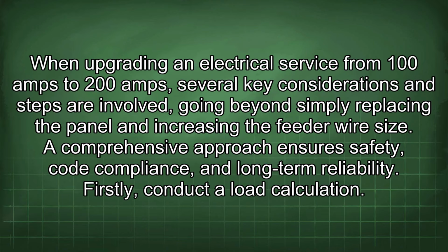When upgrading an electrical service from 100 amps to 200 amps, several key considerations and steps are involved, going beyond simply replacing the panel and increasing the feeder wire size. A comprehensive approach ensures safety, code compliance, and long-term reliability.